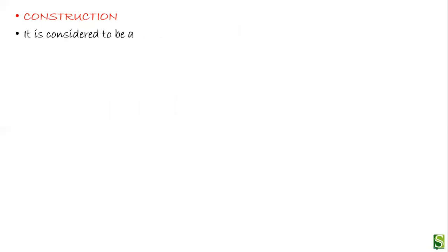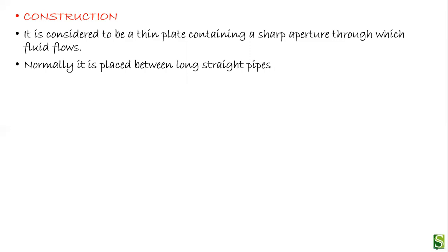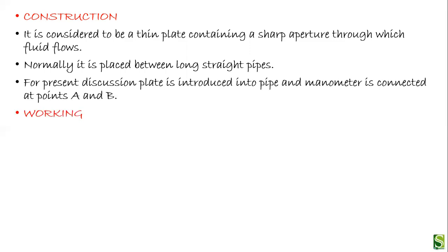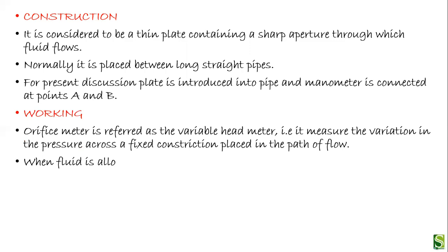The construction of the orifice meter: it is a thin plate containing a sharp aperture through which the fluid flows, normally placed between long straight pipes. A plate is introduced into the pipe and a manometer is connected at points A and B. The orifice meter is referred to as a variable head meter — it measures the variation in pressure across a fixed constriction placed in the path of the flow.